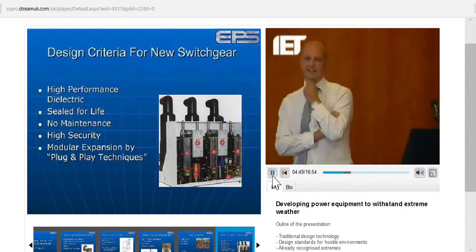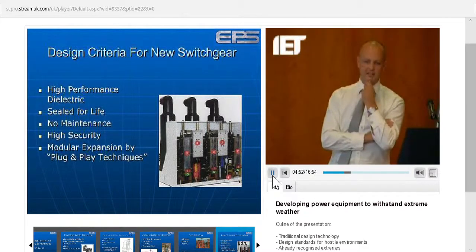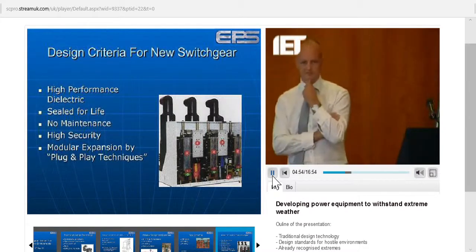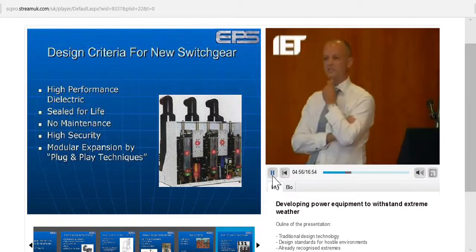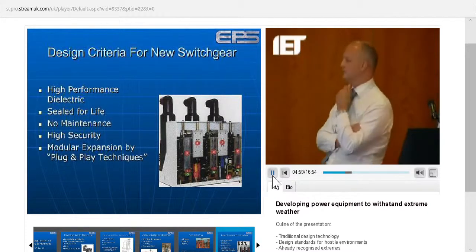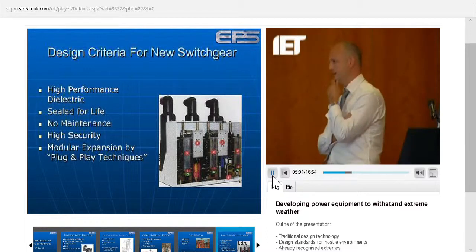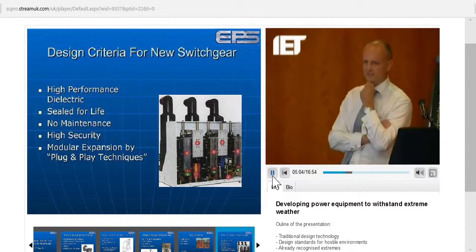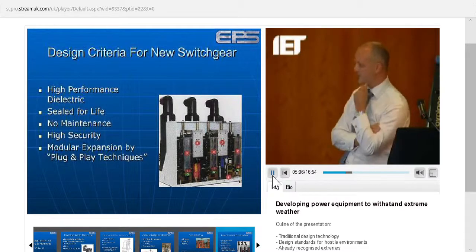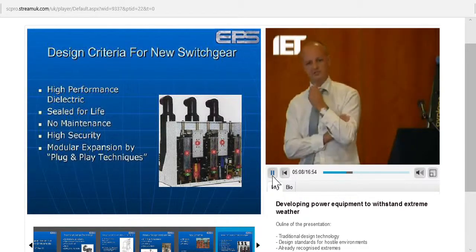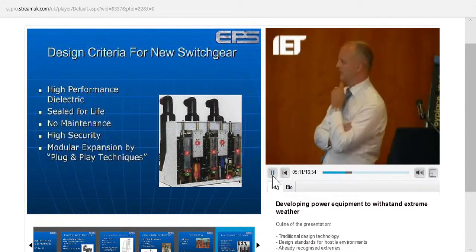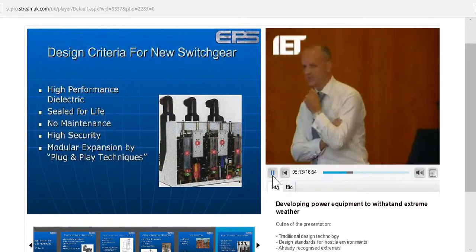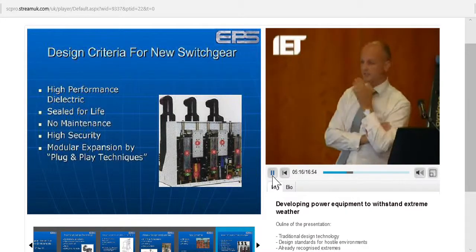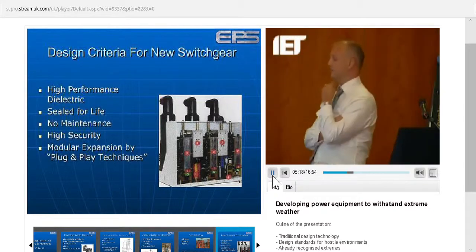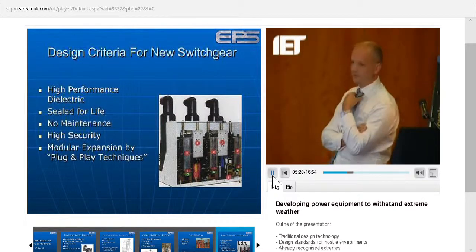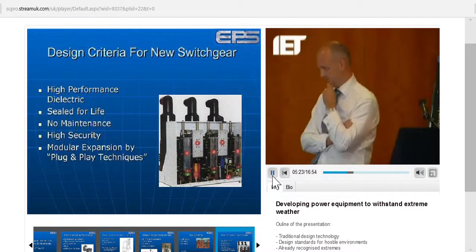There are two magnets in there, which have led to the development of a highly reliable mechanism—a magnetic actuator mechanism. We're seeing more and more of these mechanisms used on switchgear now. The magnets are extremely strong, with a life of about 100,000 operations, and they enable us to produce a circuit breaker that is effectively maintenance-free. We use vacuum interrupters and a mechanism with only one moving part, so statistically it's more reliable, and it is genuinely maintenance-free, able to perform many hundreds of thousands of operations.